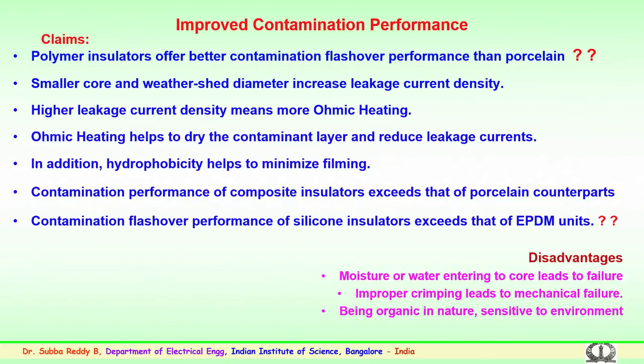The reason is that during crimping even a minor crack formation, or overload because of the procedure being followed, could later cause the insulator to shatter. These micro cracks may lead to failure of the insulator or the fiberglass rod, and the line could be thrown away. So, this is a very important factor, particularly during the manufacturing stage, where it has to be taken into consideration.